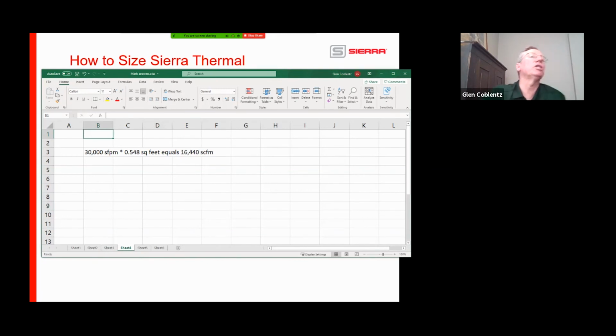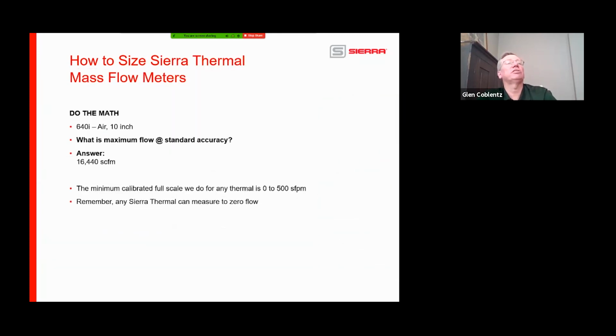And the question that we just did, 30,000 standard feet per minute. That's the maximum full scale for a 640i times the area of the pipe in square feet gives you 16,440. So nice job. I've seen a lot of other correct answers as well, so I appreciate the participation there. Got just one more to go.